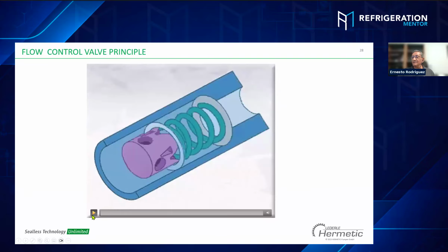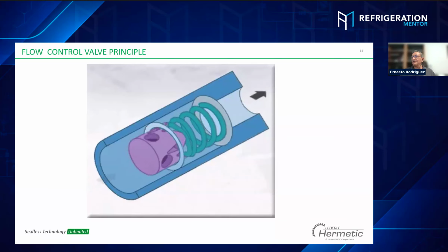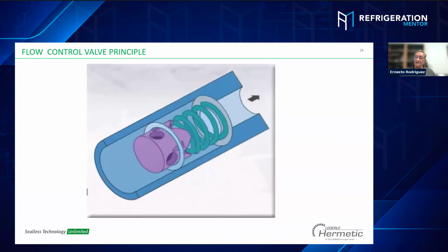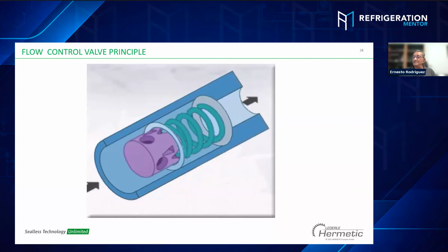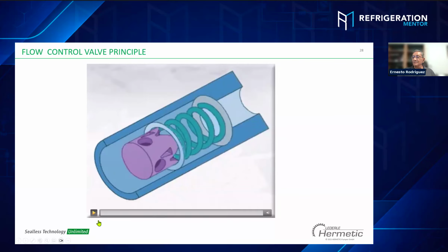How does the thing work? Basically, I have it right here. The pump is pumping the fluid. The system is equalized, balanced, the coils are perfect. But at some point, the system is demanding more fluid. More fluid means the pressure is going to increase on the coil or evaporator closer to the pump, due to less pressure drop. To prevent this problem, because tunnel number one and tunnel number three have lower pressure, this is going to modulate more and equalize all the pressure across the tunnels.